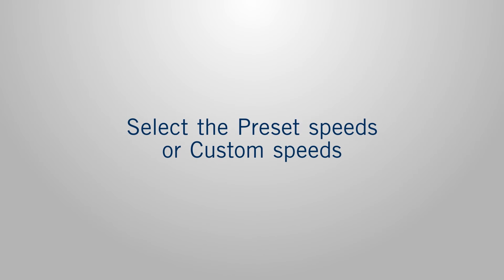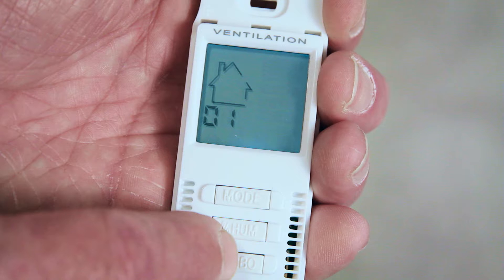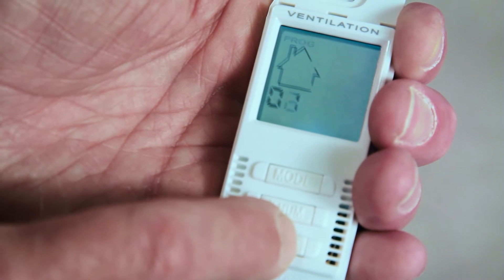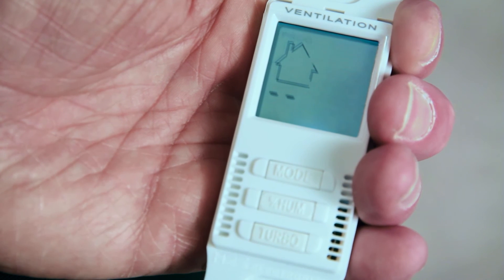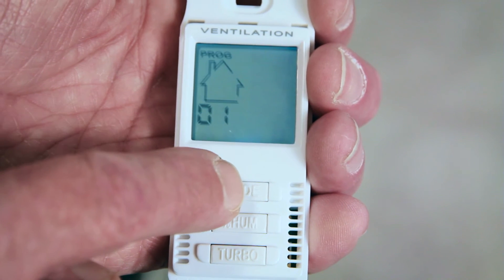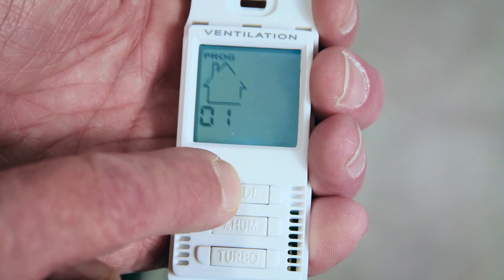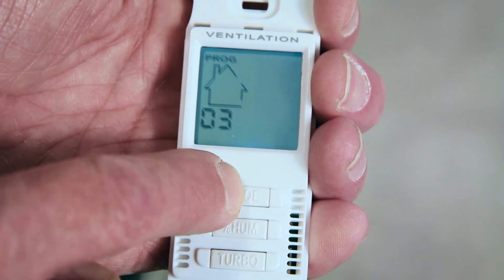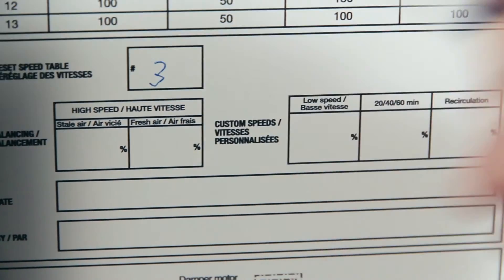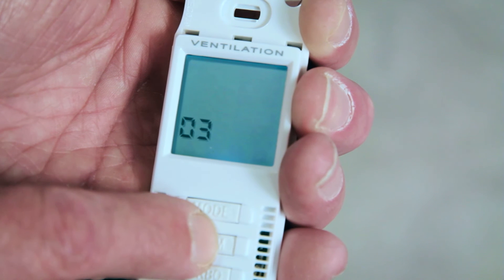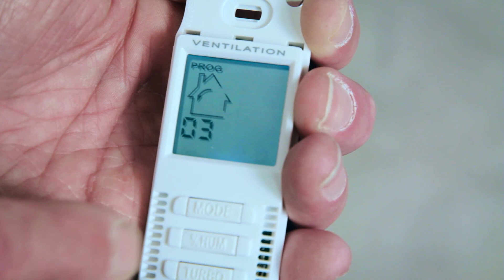01 speed value, which is a preset value, will appear on screen. Press on the lower button to lower the value in order to access custom speed settings. Press on the upper button to raise the value and reach the preset table value you need. Write the selected preset speed on the label as it will disappear by pressing the accept button. Press the middle button to accept the chosen selection.